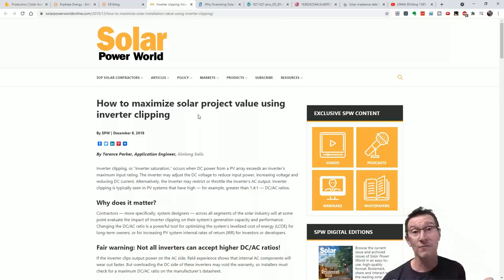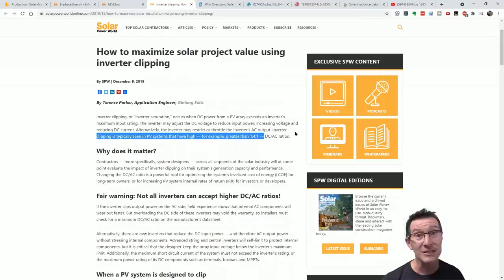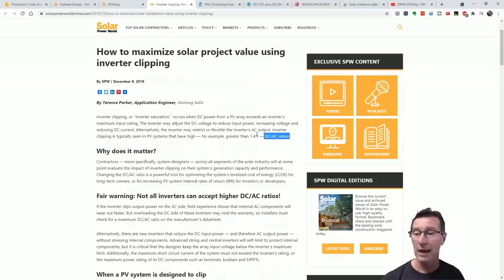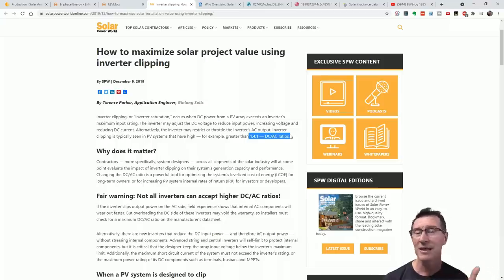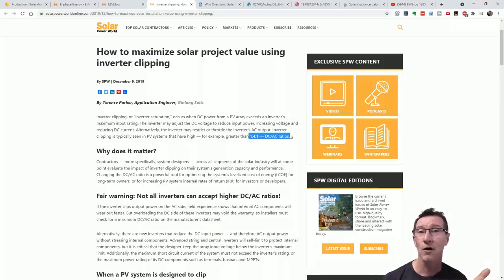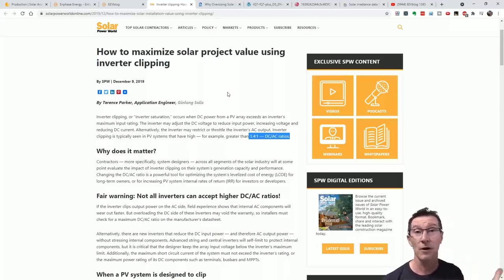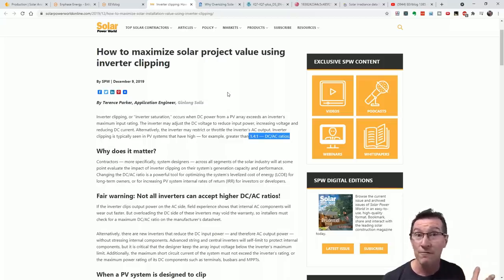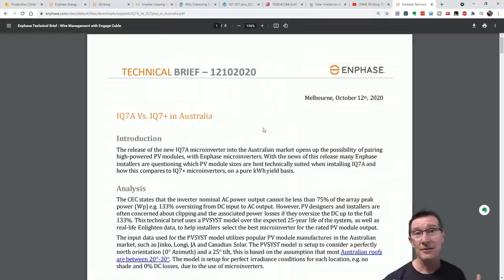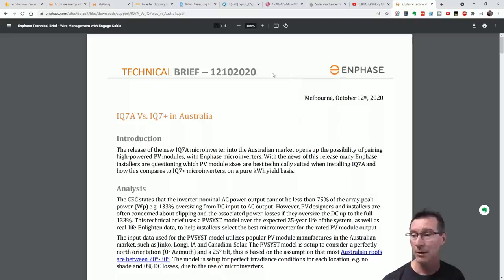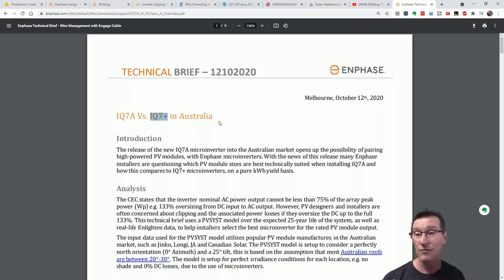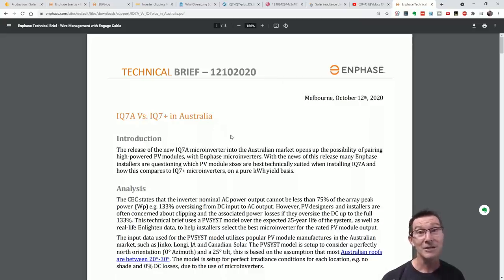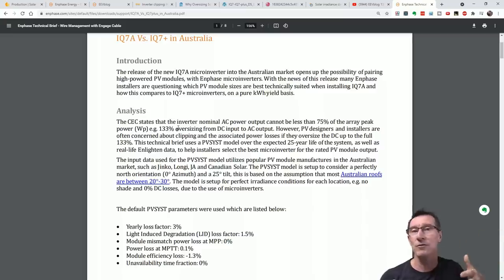Some people claim, and probably rightly so, that you might actually get increased energy output, not power but increased energy output over time, increased energy output over the life of the system by actually using a derated microinverter, i.e. a 295 watt microinverter on a 370 watt panel. In this particular case it's called the DC to AC ratio. In my case it's 295 watts peak divided by 370, that's about 80% or a 1.25 DC to AC ratio, and that's actually fairly average in the market.